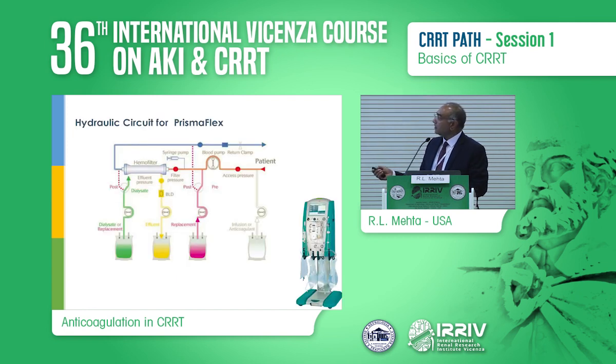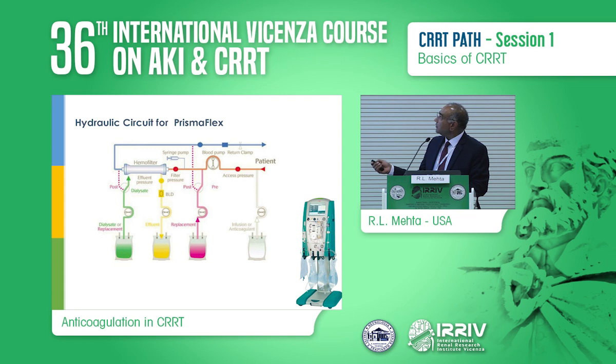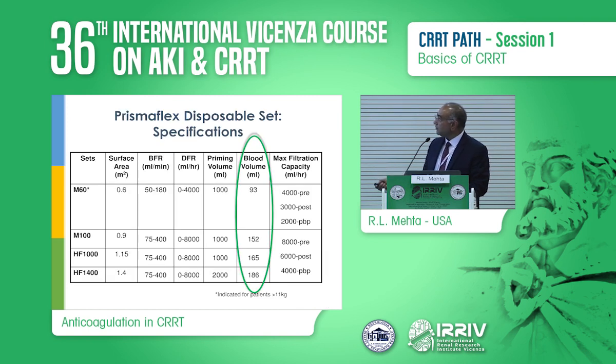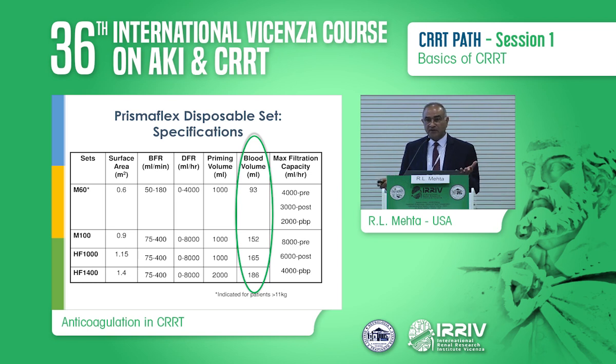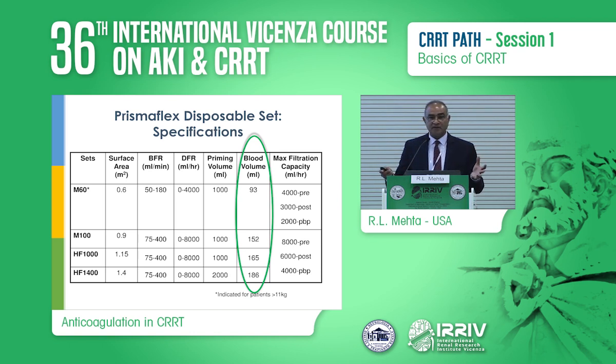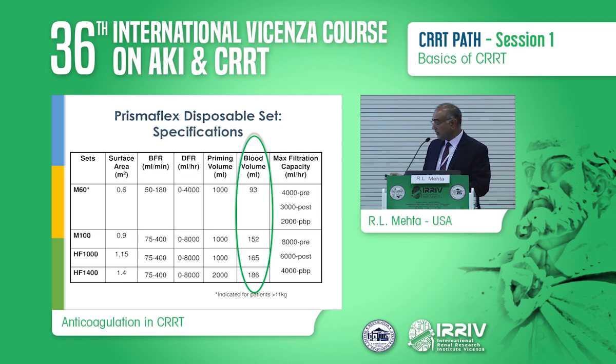This is a reflection of the PrismaFlex circuit, because that's the device we've been using for many years. You've got the blood going in and the return overall. These are the membranes available for the PrismaFlex — you can see the blood volume and capacity. The circuit size varies depending upon what membrane and what machine you're using. The first aspect is to familiarize ourselves with how big the membrane and circuit are, because that's going to influence your anticoagulant strategy.